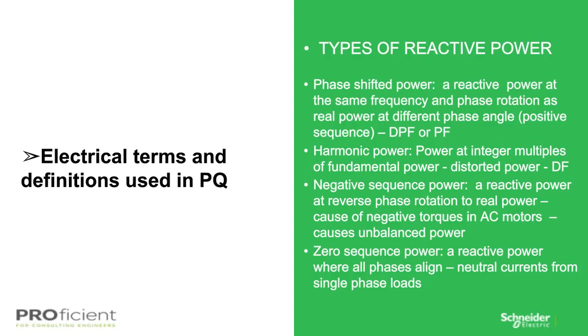Second is harmonic power, which is caused by rectifiers, also known as converters, which change power from AC to DC for use inside the product. It is typically defined as the distortion factor, DF, and generally harmonic discussions refer to percent THDI or percent THDV, which I'll get into a little more as we proceed in this discussion, to indicate both harmonic amplitudes, which is the total harmonic distortion current as a percent, as well as the total harmonic distortion voltage as a percent.